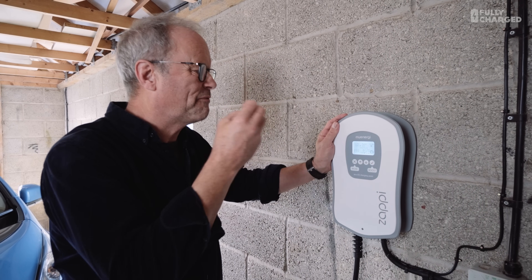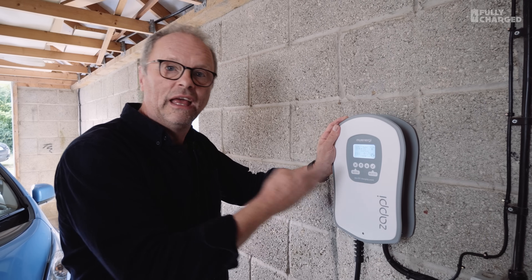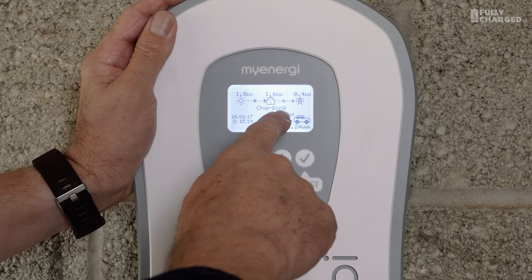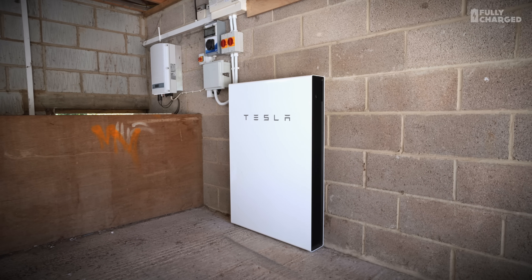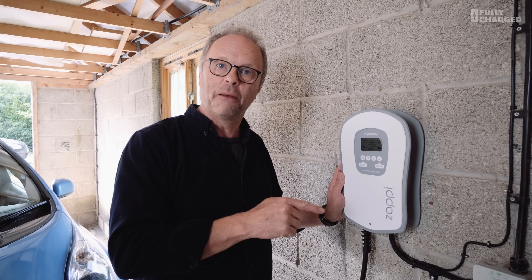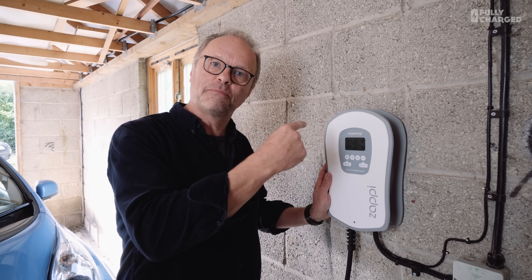It's a very simple system to use and you can override it at any time. If the car is very low on charge and it's going to take too long, I can switch it to fast mode and it will immediately start taking electricity from the grid, charging at a much higher rate — now pulling 3.8 kilowatts. There was an added complexity here with the Tesla Powerwall, which required careful recalibration and a firmware update. It's been a really good learning experience for Zappi.